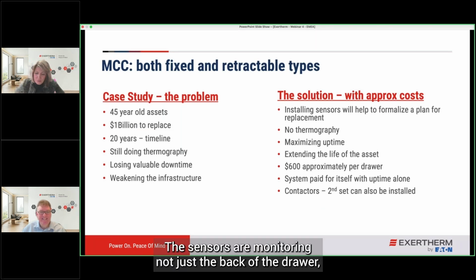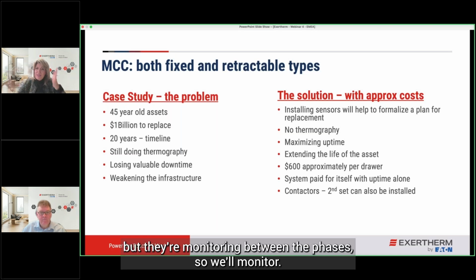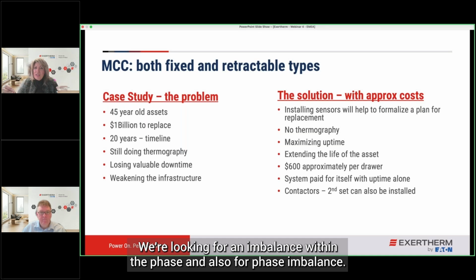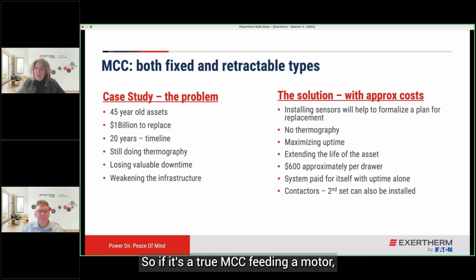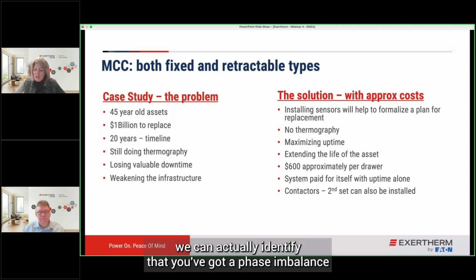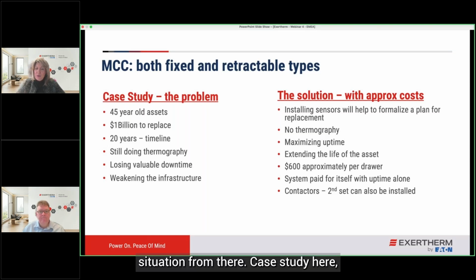The sensors are monitoring not just the back of the drawer, but also between the phases. So we're looking for an imbalance within the phase and also for phase imbalance. If it's a true MCC feeding a motor, we can identify a phase imbalance situation from there.